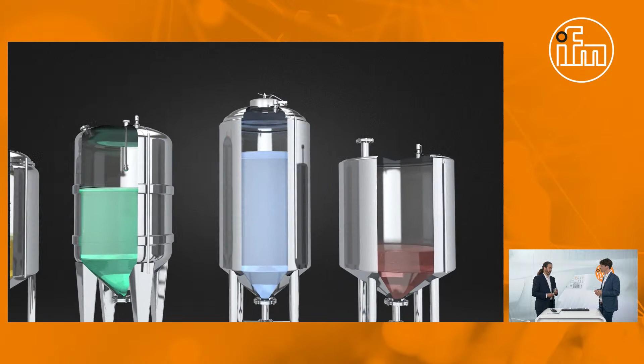Now with the non-contact radar solution, installed on top of the tank in a process connection, we don't have contact with the product, and with this narrow beam angle we have the possibility to ignore all those constructions, because the beam angle is so narrow we don't even see them, even with very tall and high tanks. It doesn't hit the agitator. Exactly, it is not disturbed by the moving agitator, clearly an advantage compared to other technologies in this case.